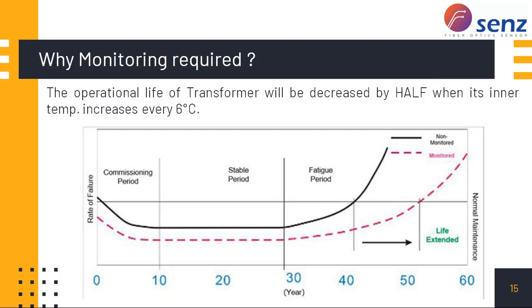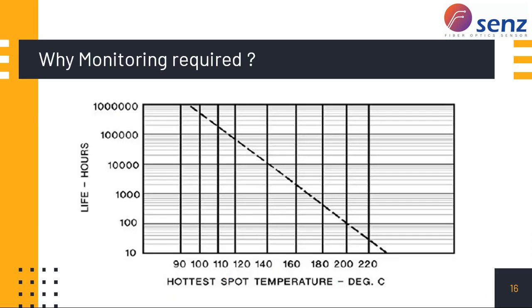In case you are monitoring a transformer temperature, for every 6 degrees increase in the temperature of the transformer, we will reduce the life to half. So you basically can extend the life of the transformer over 50 years if you are monitoring and taking action in case high temperature is there, in hours and the temperature of the windings for the transformer.